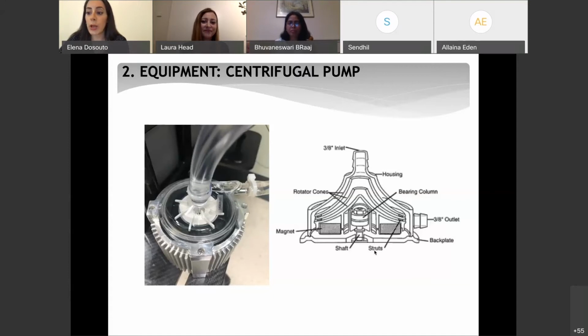So the good, but also bad thing about centrifugal pumps is that they are non-occlusive and they're preload and afterload dependent. So this means that when the impeller is not spinning, fluid can flow in both directions, so in the right direction and in the wrong direction. So if for any reason the pump stops spinning and your line towards the patient is not clamped, you can get retrograde flow, which again is not ideal.